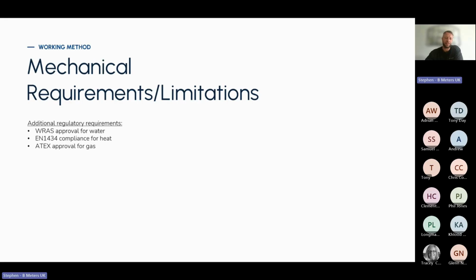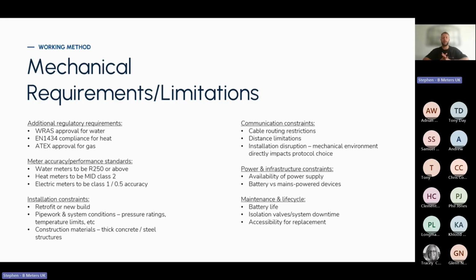Mechanical requirements and limitations are important when realistically choosing meters, because of additional regulatory requirements. Not all meters will have these, like WRAS approval, which most water meters will need if designed for potable water. EN 1434 compliance for heat is almost predetermined, while ATEX approval for gas is probably not needed. That's what really channels your selection. For example, I recently had to find a WRAS approved DN40 water meter, and it had to be a particular mag flow meter that was MID 001 and WRAS approved. Would I have selected that from the outset? Obviously not - it's very expensive, but regulatory requirements will push you down an avenue to find the correct meter for your project.